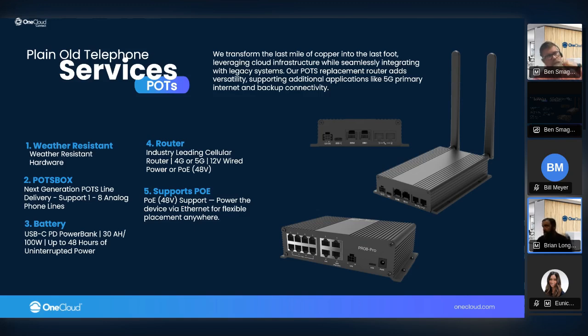Really, as we talked about earlier, the big requirement is battery backup - that's one thing they're going to want when you hook one of these up to a fire panel. It does need a backup battery, a secondary power supply. So at minimum, our devices will run at full capacity for around 24 hours, which is the minimum, but typically with standard usage we've seen them run for about 48 hours. The 2-port will run for well over 48 hours. Right now we support 4G and 5G - 4G in the 2-port, and 5G in the PR18 that's coming out soon.